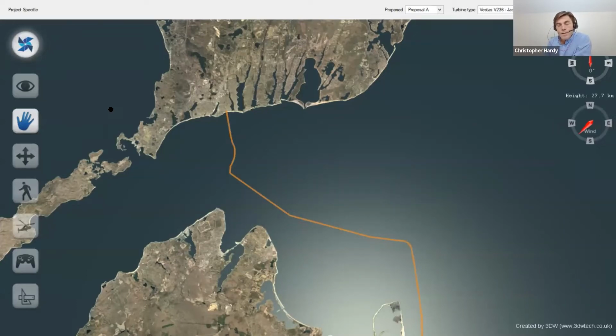In terms of technology, Mayflower Wind's preferred technology is high voltage alternating current, or HVAC, though we're also evaluating high voltage direct current, or HVDC, which typically has less power loss over long distances. However, it's traditionally more costly and has more limited supply chain options. Engineers who have assessed both technologies typically consider a range between 60 to 75 miles as the point at which HVDC becomes the better choice.